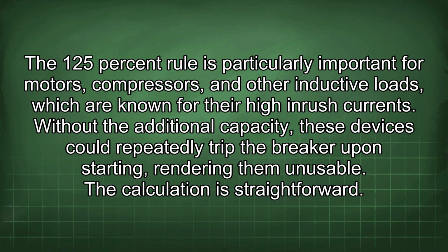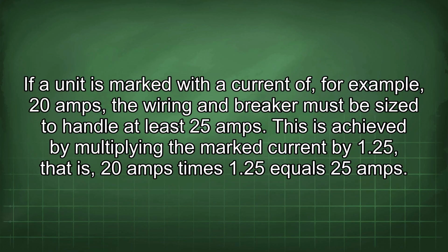The 125% rule is particularly important for motors, compressors, and other inductive loads, which are known for their high inrush currents. Without the additional capacity, these devices could repeatedly trip the breaker upon starting, rendering them unusable. The calculation is straightforward. If a unit is marked with a current of, for example, 20 amps, the wiring and breaker must be sized to handle at least 25 amps. This is achieved by multiplying the marked current by 1.25, that is 20 amps times 1.25 equals 25 amps.